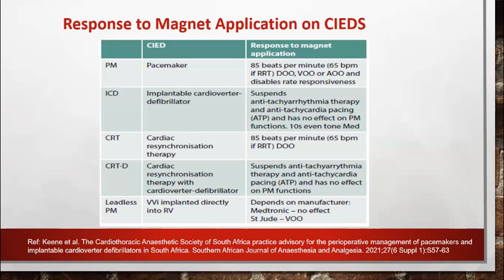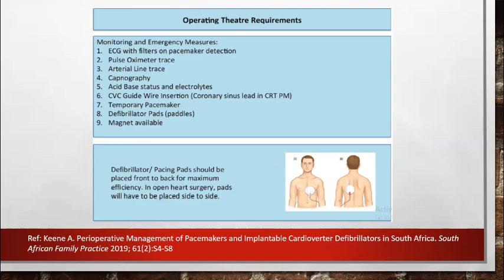Now the operating theater requirements, monitoring and emergency measures: ECG filters and pacemaker detection. This is very important, the ECG should have a filter. Pulse oximeter trace, arterial line, capnograph, acid-base status and electrolytes, CVC guide wire insertions, coronary sinus lead for CRT pacemakers, defibrillator pads, magnet available. Defibrillator and the pacing pads should be placed front to back for maximum efficacy. In open heart surgery, pads will have to be placed side to side.